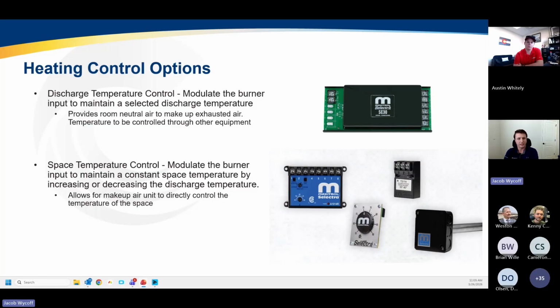The second option would be space temperature control, where the burner actually ramps up and down by increasing or decreasing the discharge temperature to control to a specific space temperature set point. This is great because it allows the makeup air unit to directly control the temperature of the space, get you a tight set point without relying on auxiliary heating equipment to actually maintain the set point in the space.